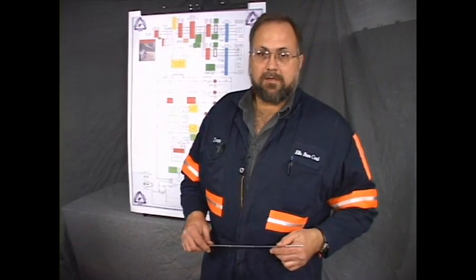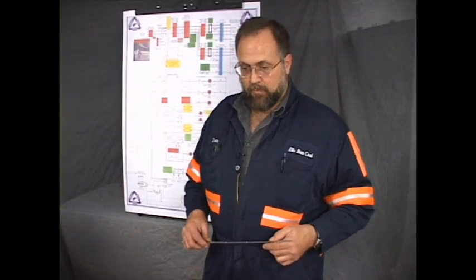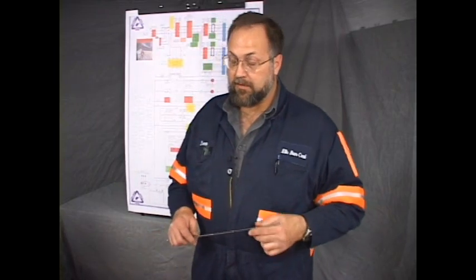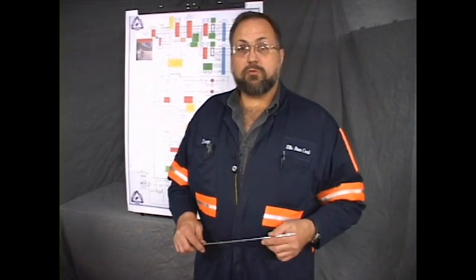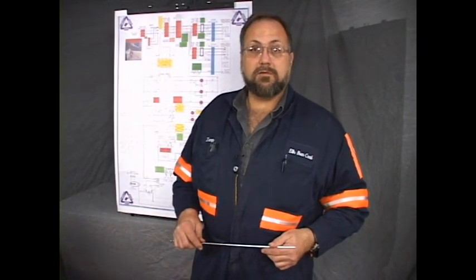Instead of making continuity tests here, we're going to take some voltage readings. You can work on energized equipment in a limited fashion, troubleshooting only, by wearing low and medium voltage gloves. And the only tools you can really hold in those gloves is your test instruments. And that's what we're going to do now.